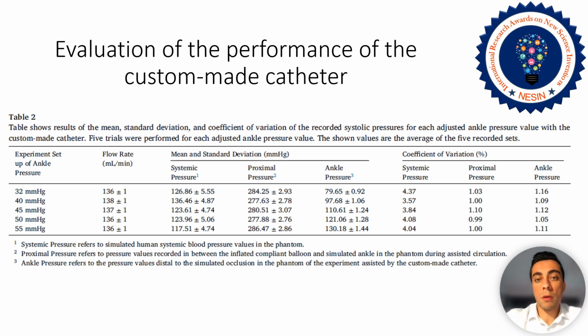Table 2 shows results of mean, standard deviation, and coefficient of variation of the recorded systolic pressures for each adjusted ankle pressure value with the custom-made catheter, of course. 5 trials were performed for each pressure value. The shown values are the average of 5 recorded sets. In Table 2, the results have shown that the systolic pressure values that were measured between the isolated arterial branch and troubled area can be maintained above 270 millimeter mercury.